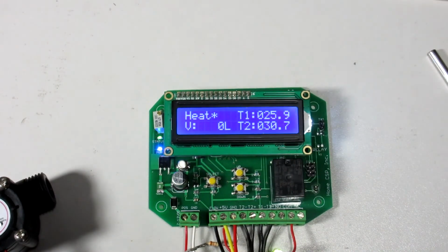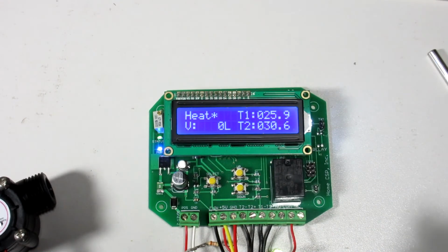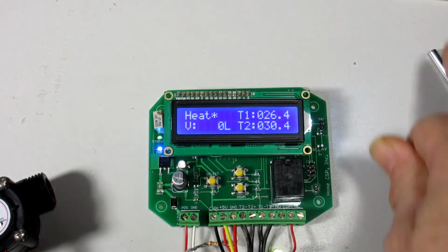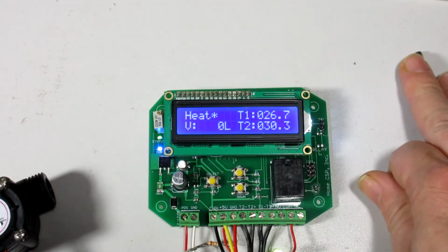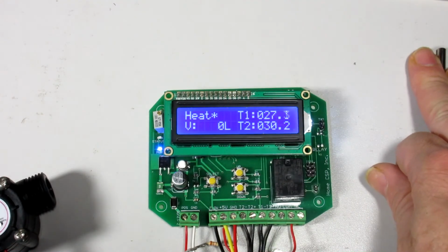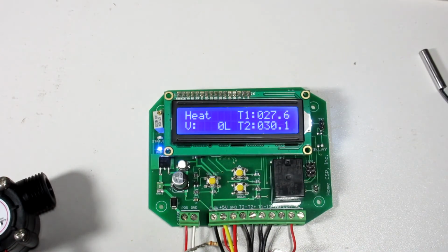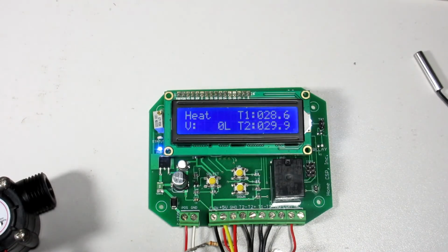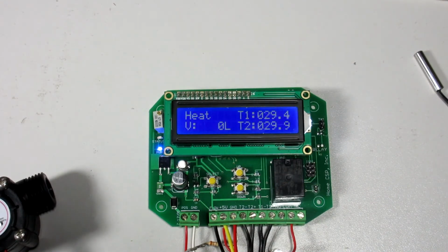So, I can also take T1 here, and I'm going to raise its temperature. Put a little bit of heat on this, keep this one above 30. And once the difference got too small between the two, it shut off the output just like it should. So that's the basic temperature differential operation.